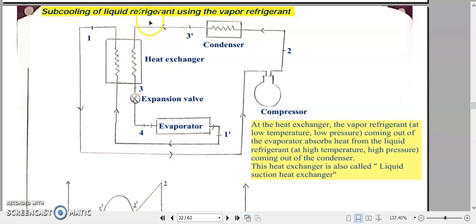This liquid refrigerant coming out from the condenser is getting subcooled at this heat exchanger. Why? It is going to reject its high heat onto the low temperature, low pressure vapor refrigerant, which is coming out from the evaporator. So this heat exchanger is also called a liquid suction heat exchanger. What does that mean? The liquid form of this refrigerant is rejecting heat, or getting subcooled, by the vapor form of this refrigerant.